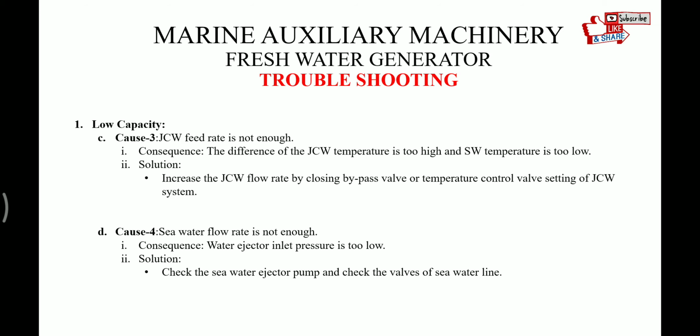Third cause is jacket water feed rate is not enough, and the consequence is the difference of the jacket cooling water temperature is too high, and the seawater temperature is too low. And the solution for that is increase the jacket cooling water flow rate by closing the bypass valve or the temperature control valve setting of the jacket cooling water system.